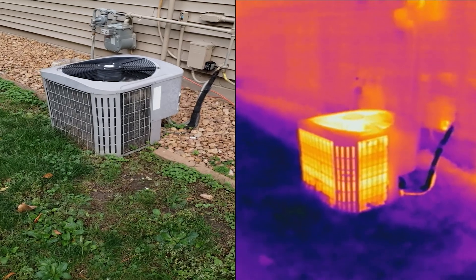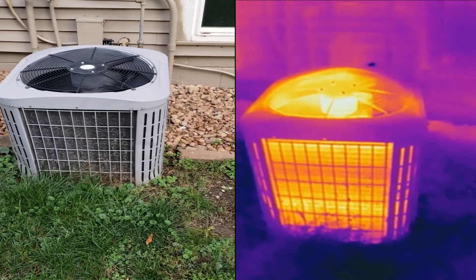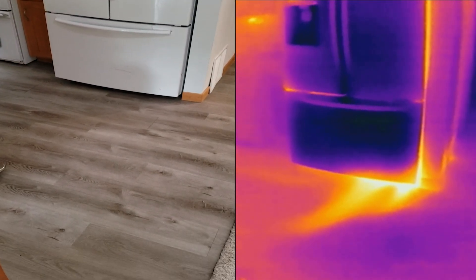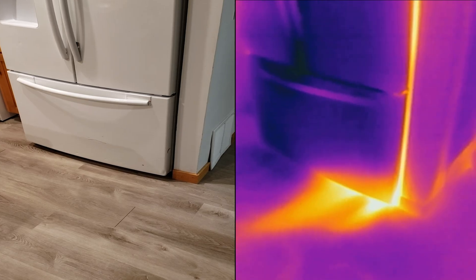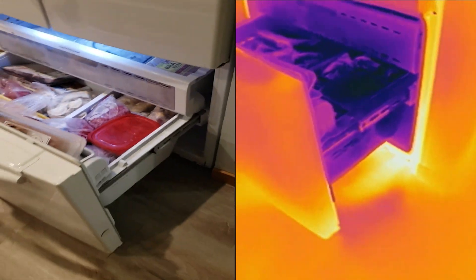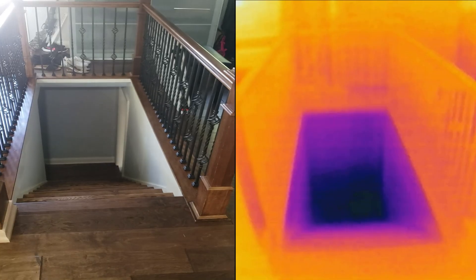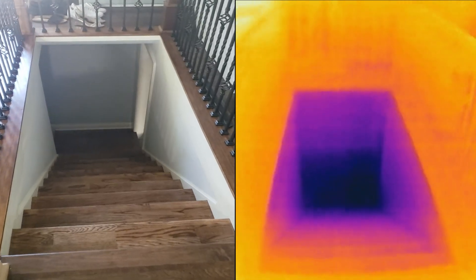Here is an example of what a split unit condenser looks like while running. The motor is another component that gets rather hot, and if a motor is burnt out, it would probably light up twice as bright on the camera. On a refrigerator, the condenser fan and compressor is usually located on the bottom, and we can clearly see that the fan is pushing the hot air out on the bottom right side. As an experiment, we opened the freezer for about 30 seconds — since colder air sinks to the bottom, we see a patch of blue on the floor when the door is open. The camera also shows that the temperature is colder on the bottom of the steps leading down into the basement.